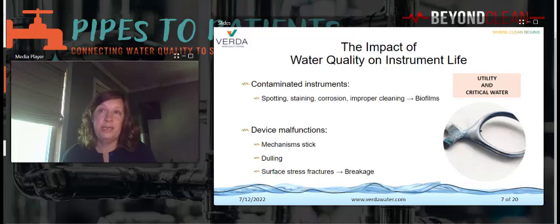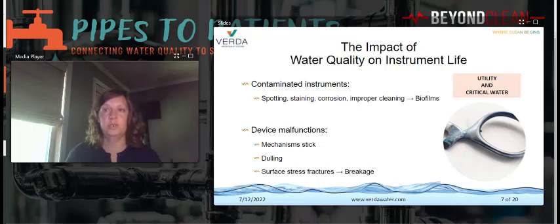Whether it's from inadequate cleaning, corrosion, stains, or spots, if an accumulated biomass of bacteria can proliferate on instrument surfaces, they form biofilms, tightly adhered to the surface and not removed easily. The outer layers of the biofilm then protect the inner layers from destruction, eventually permanently affixed to the surface of the instrument. No amount of reprocessing or recleaning can make them decontaminated and sterile for reuse. Consequently, instruments, whether critical or semi-critical, require them to be disposed and replaced.